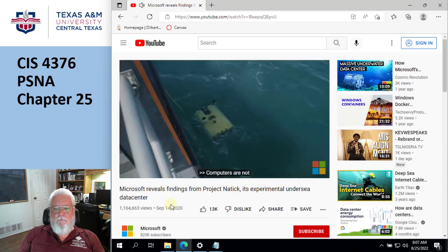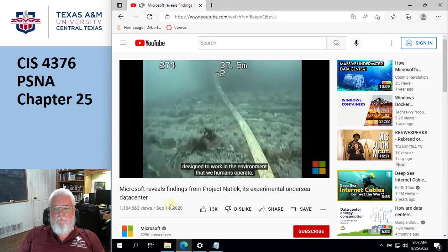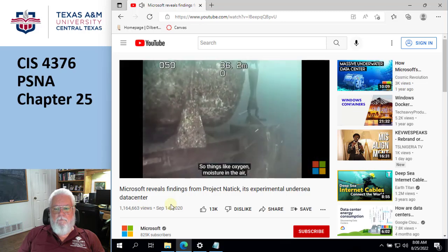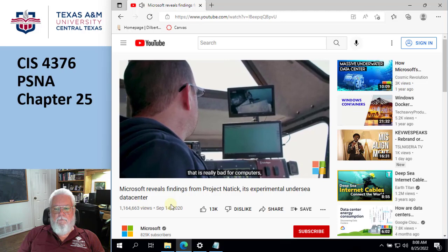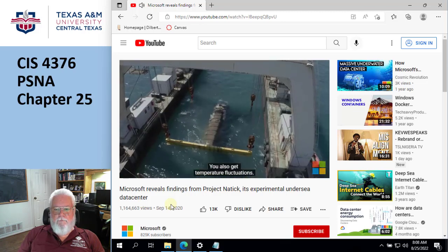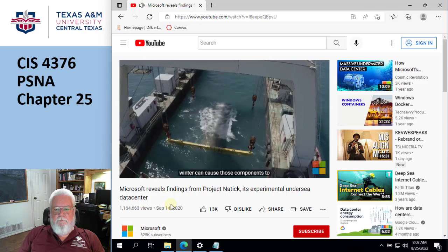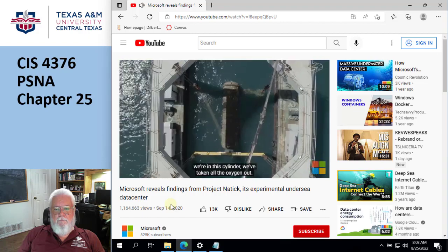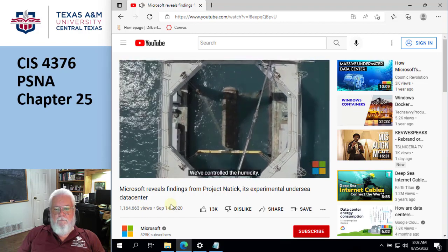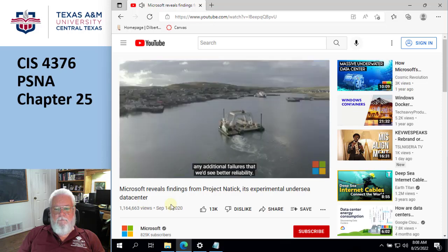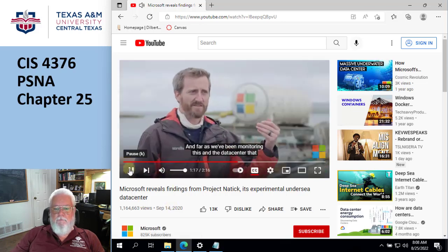Computers are not designed to work in the environment that we humans operate. So things like oxygen, moisture in the air, that is really bad for computers. It causes corrosion on the components. You also get temperature fluctuations. So the heat from night to day and summer to winter can cause those components to fail. And so we had this theory that if we're in a really stable environment, we're in this cylinder, we've taken all the oxygen out, we've controlled the humidity, no one's walking around, there's nobody bumping things or causing any additional failures, that we'd see better reliability. And so far as we've been monitoring this and...